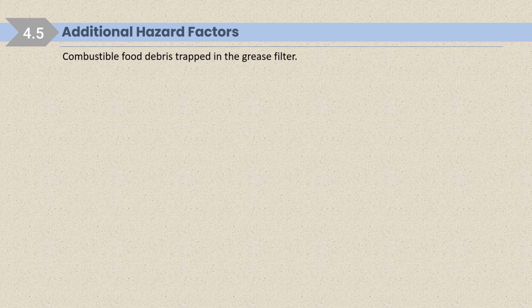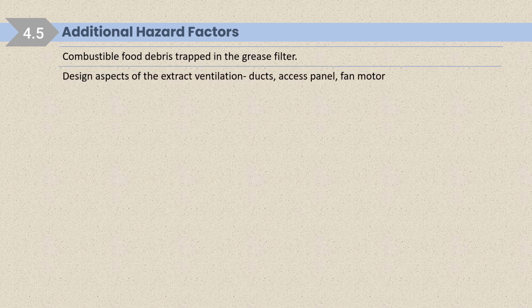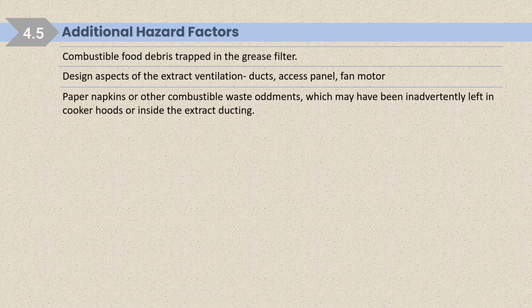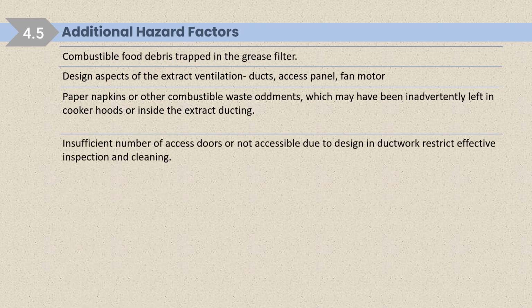Additional hazard factors: combustible food debris trapped in the grease filter. Design aspects of the extract ventilation duct, access panels, fan motors. Paper napkins, sometimes we see people use that space by mistake. Suppose someone has no idea about the exhaust duct system, and he is putting some paper napkins or any unused or storage material inside the hood, which may have been inadvertently left in cooker hoods or inside the extract ducting.